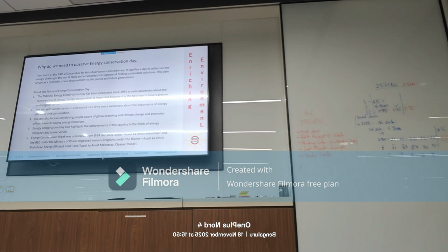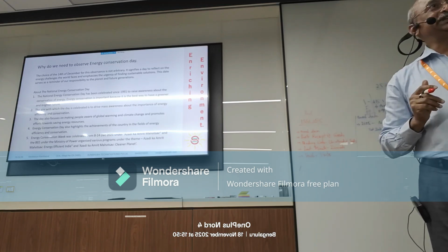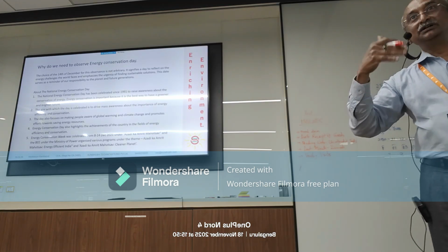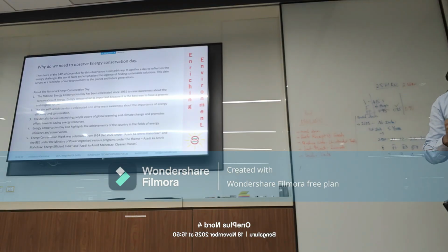As the maintenance team, this is what I would be interested in. As an energy auditor, as management, they're interested in savings. They're happy if they're getting 0.3 unit savings. But as a maintenance team, it's a cause of concern. Initially, you might get a good tag. You might even get an award for saving that 0.3 units. But gradually, you will find a serious issue coming up there at the back.